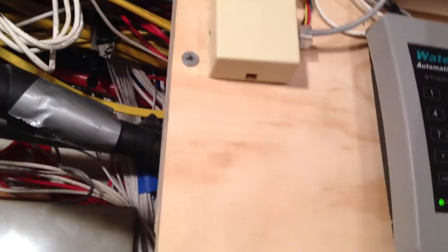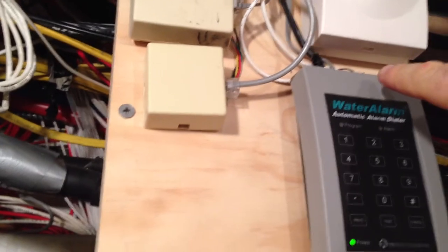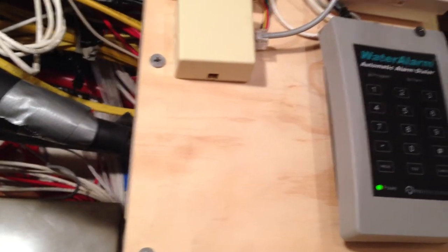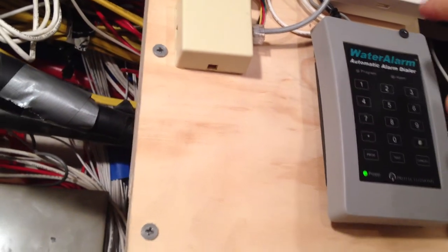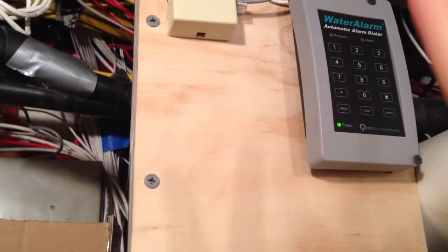So let's take a look at one of the sensors. Basically you're connecting just these, I think it's 18 gauge wire I have. It's 18 slash two wire, 18 gauge, two wires. And you just connect one to each of those connectors and you run it across. And you want to run it into an area, the lowest part. For instance, in the boiler room, we have a lot of piping here.